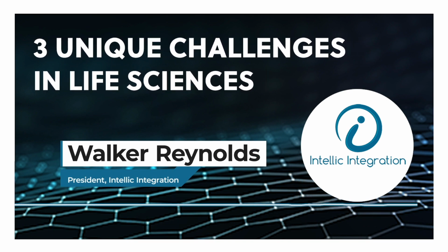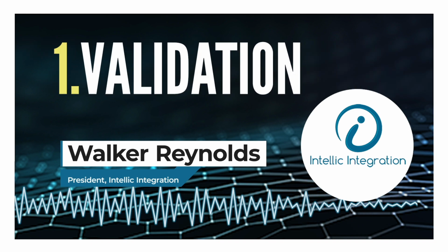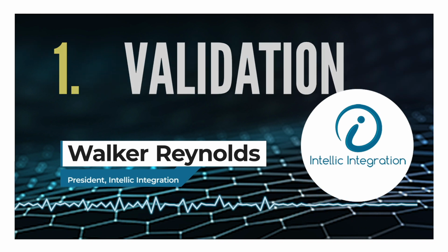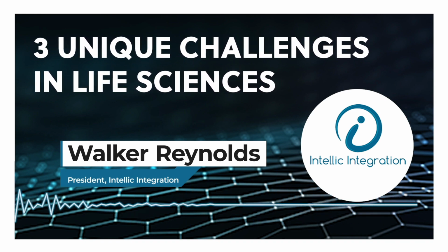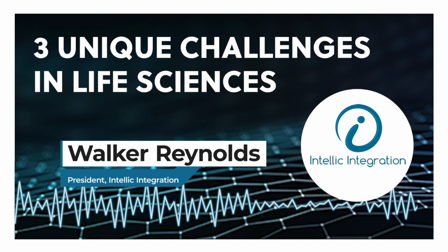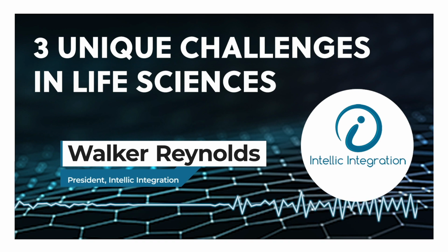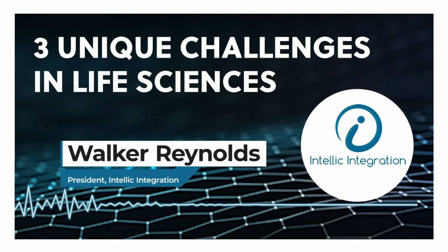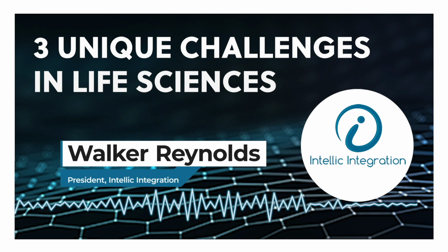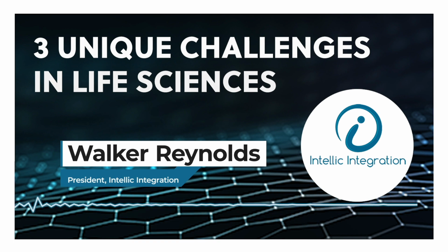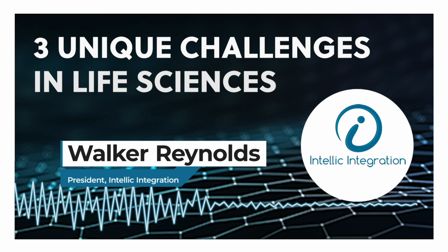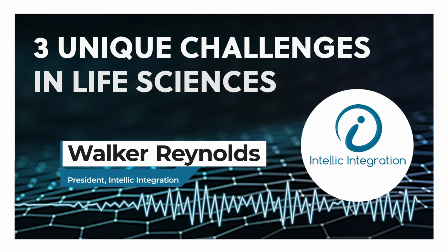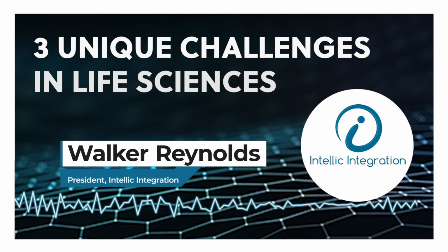So number one, validation, okay? If you've never worked in life sciences or pharma, one of the things that you have to do in all life sciences automation projects is validate every single data point at every exchange. Let's say I've got a PLC that talks to an HMI. I have an OPC server that talks to that PLC, and then I have a SCADA system that talks to that OPC server. You have to validate every single data point at every single handoff in pharma.